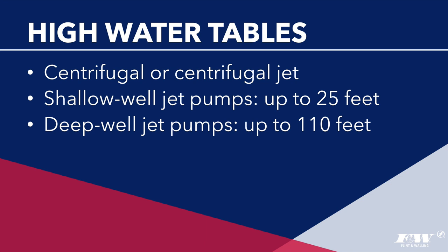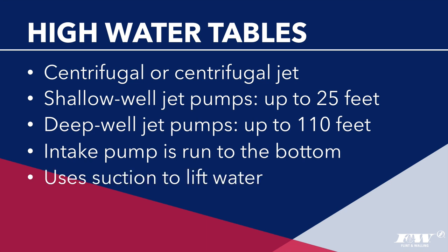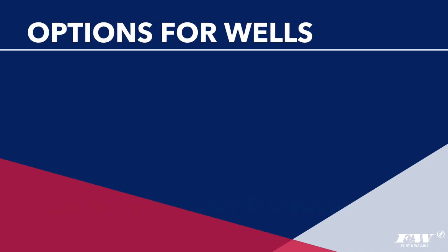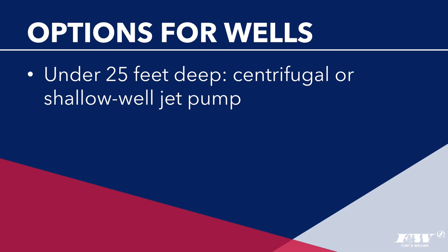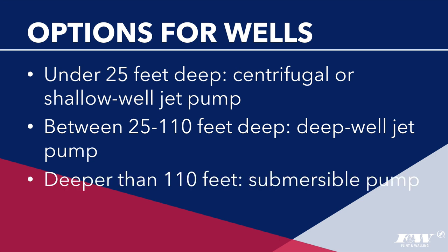Instead of lowering the pump into the well, jet pumps run an intake pipe to the bottom and use suction to lift water out. There are limits to suction lift, which is why submersible pumps are required for wells deeper than 110 feet. In summary: for wells under 25 feet deep, use a centrifugal or shallow well jet pump; between 25 and 110 feet, use a deep well jet pump; deeper than 110 feet, use a submersible pump.